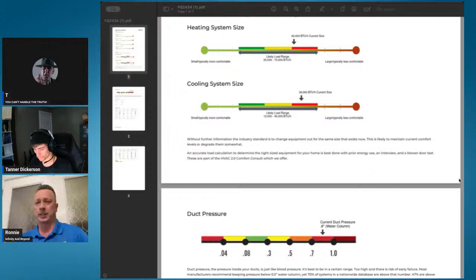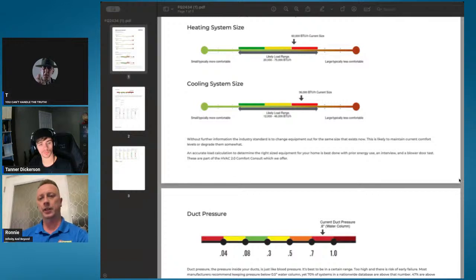I said, but you have a 4-ton duct system, and if we go with a multi-speed unit, which is like $500 more than the standard on these hybrids, plus he's got a 3,600 square foot house, so in the heating season that 48,000 BTU might carry the whole house. What'd you say, 12 degree design? Yep, 12 degree. So maybe the propane comes on below 15 degrees.